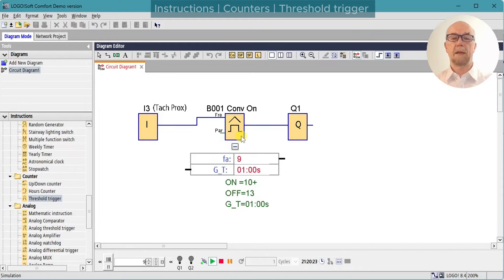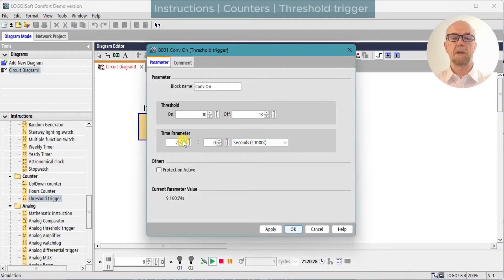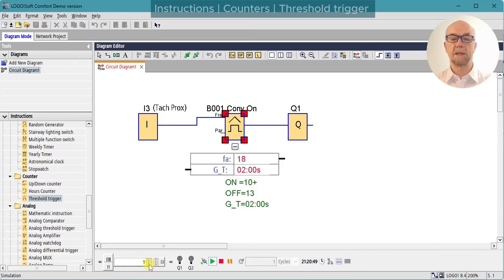We can look at how the gating time affects the setup. Setting the time parameter to two seconds to make the math easy, we can see that with a 9 hertz input signal we're getting 18 counts per two seconds. With the threshold still at 10, if we drop down to 5 the output is on; drop to 4 and the output turns off; go back to 5 and it turns on again.